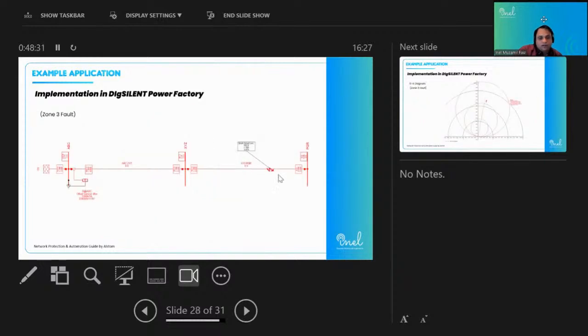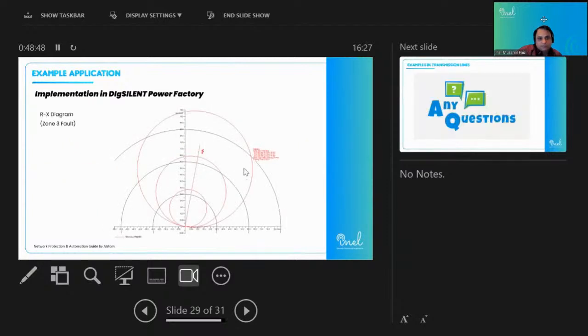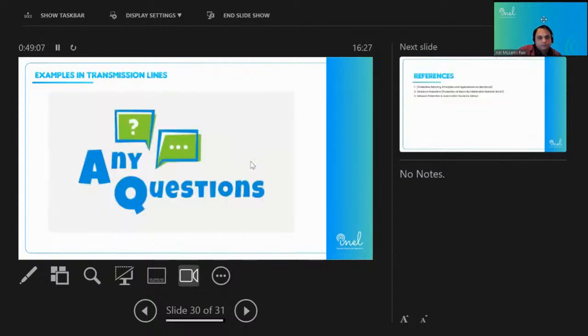Similarly, I'm applying a fault for zone 3, which is beyond 50% of this line, and in this case this relay will detect it as a zone 3 fault and operate with the pre-decided time delay. This is a zone 3 fault. This fault point shows that it is not in the zone 1 region, not in the zone 2 region, but in the third region. So this is the time of operation of the relay for the zone 3 fault. This is all from my side. Thank you.